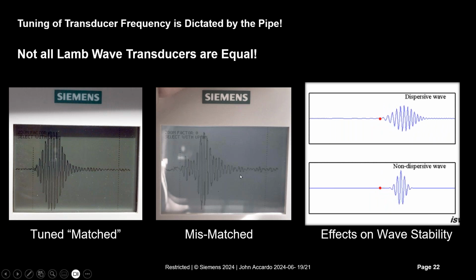If you're not matched to the pipe, or if you're using a shear wave, you can get a very poor quality wave shape, and you end up with a dispersive wave. And as that signal moves, the shape changes, and you can see it spreading out at the top there. And now your calculation of where the arrival point of the signal is changing. And so you'll get errors in your speed of sound measurement. Notice that the X on that photo in the middle there is not in the right place. It's not where the signal starts. It's off to the left a bit. And that's because the slope is so terrible there at the beginning of the signal. So tuning the transducers to the pipe is critical to get the proper wave shape.